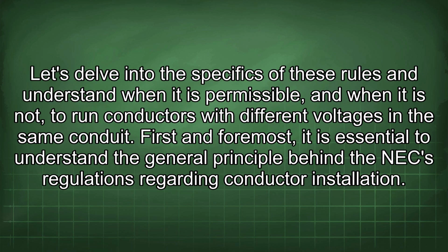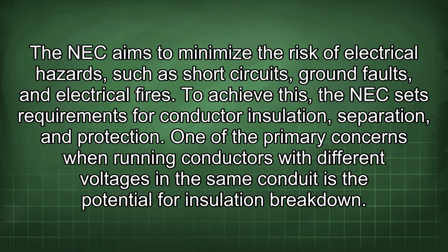Let's delve into the specifics of these rules and understand when it is permissible and when it is not to run conductors with different voltages in the same conduit. First and foremost, it is essential to understand the general principle behind the NEC regulations regarding conductor installation. The NEC aims to minimize the risk of electrical hazards such as short circuits, ground faults, and electrical fires. To achieve this, the NEC sets requirements for conductor insulation, separation, and protection.